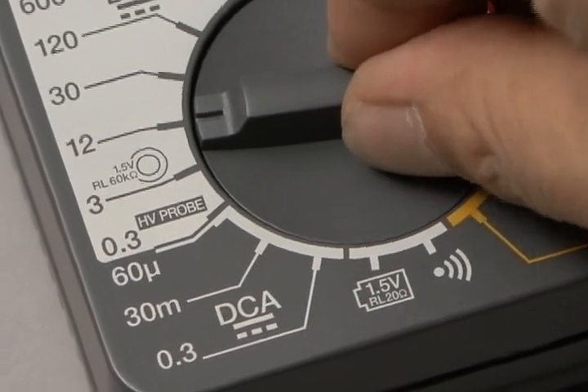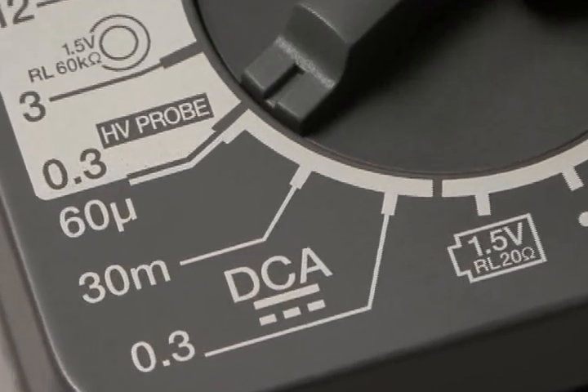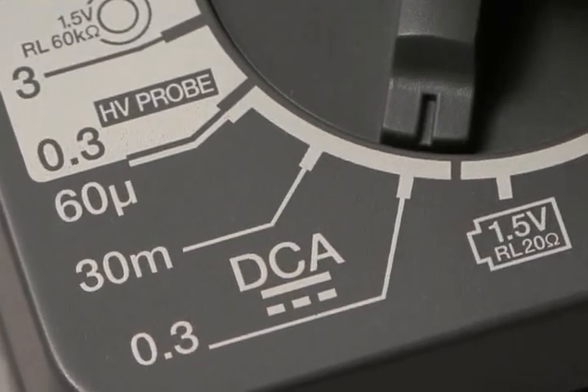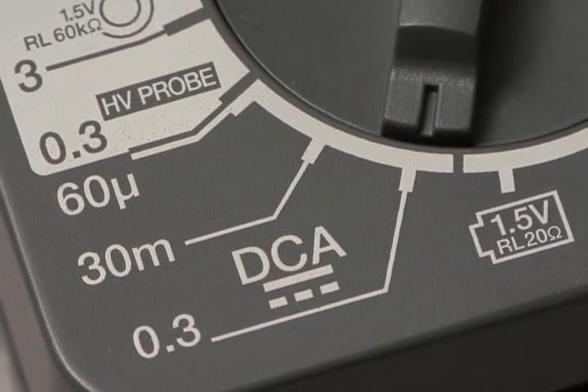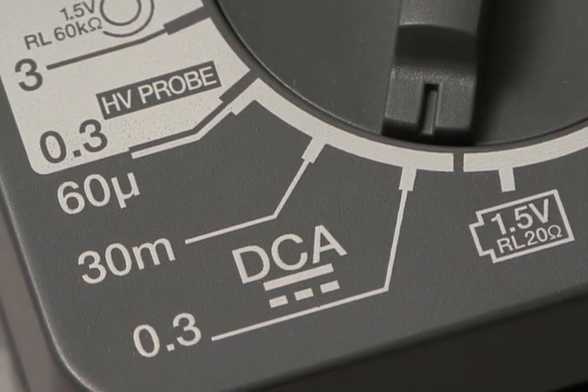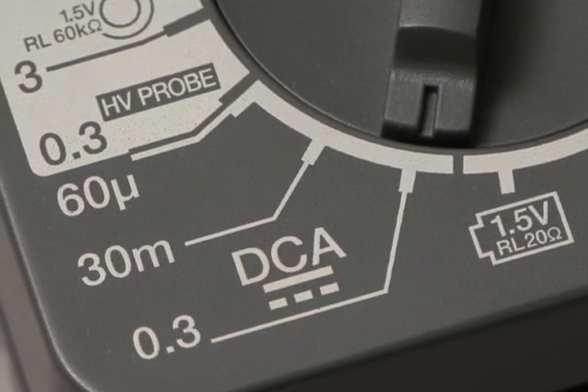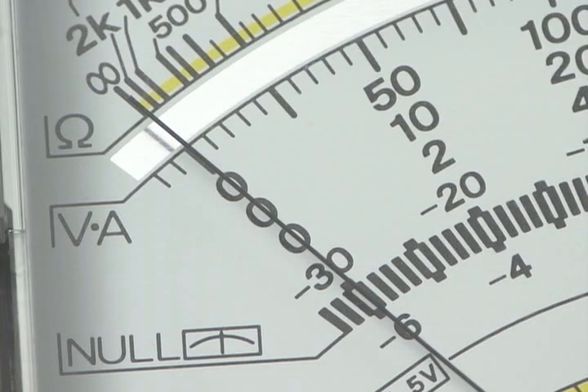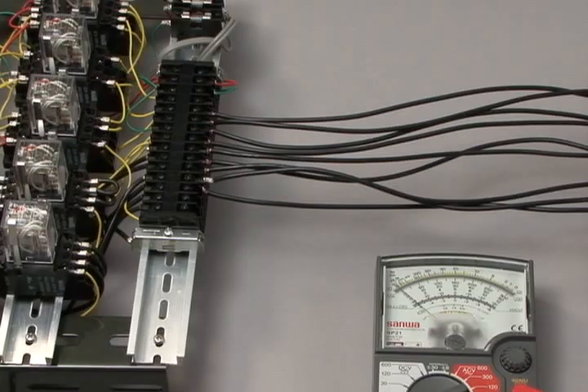Set the rotary switch to DCA. A measurement range of less than 30 mA suffices for measuring the sensor's output current, but when the range of the current is unknown, set the range to maximum. Make zero-level adjustments before starting current measurement.